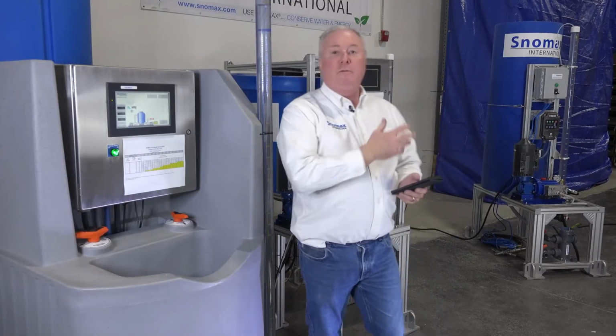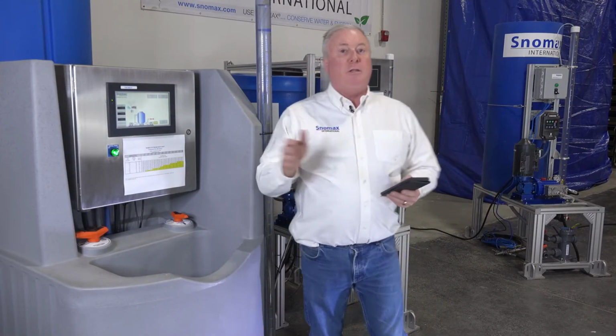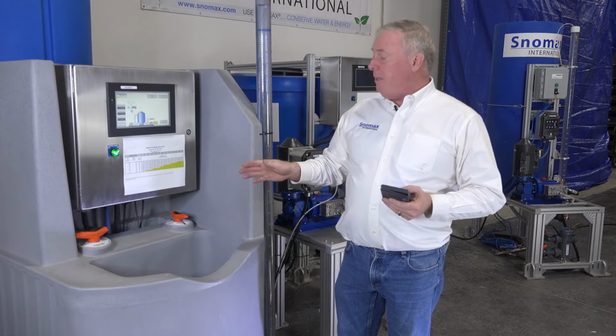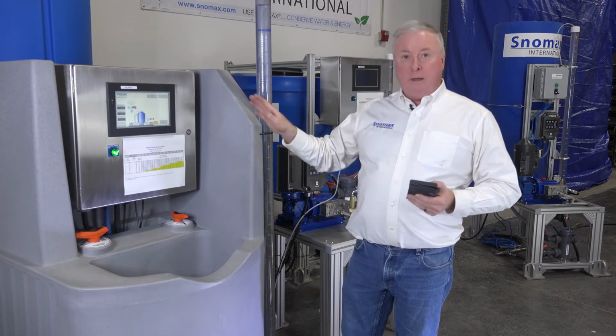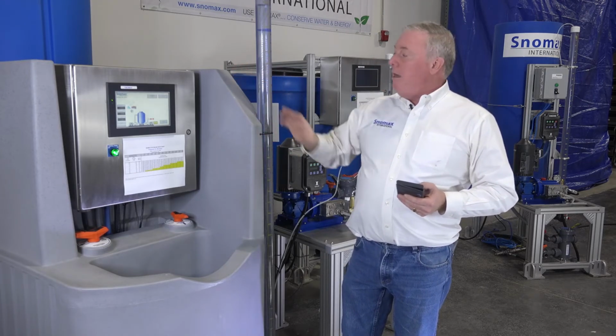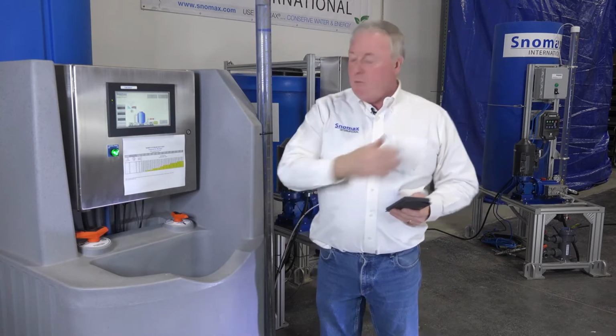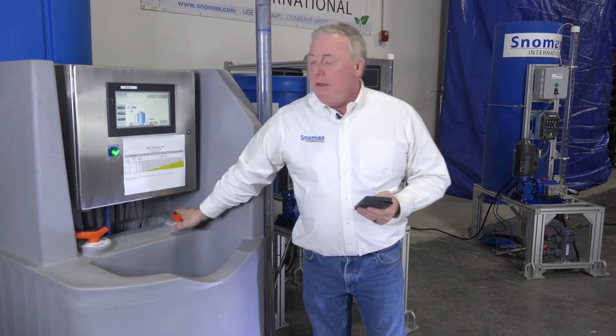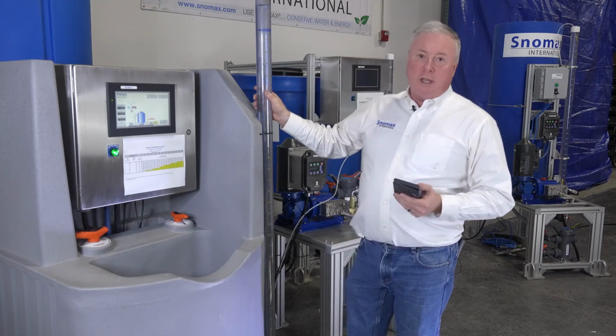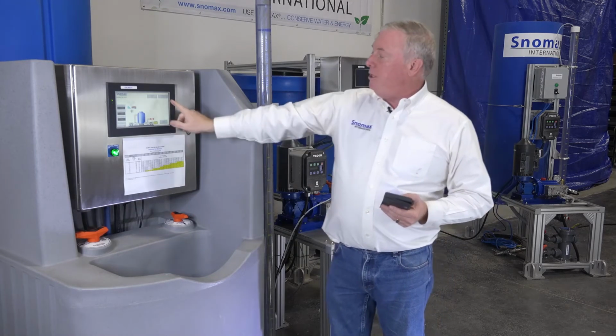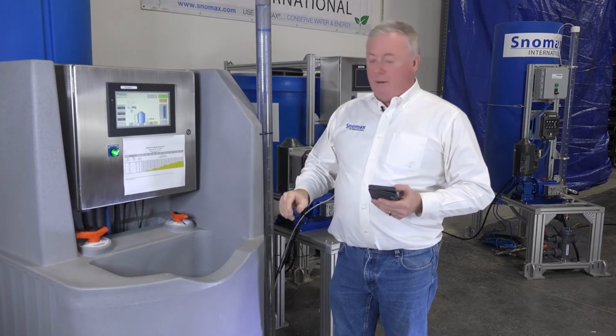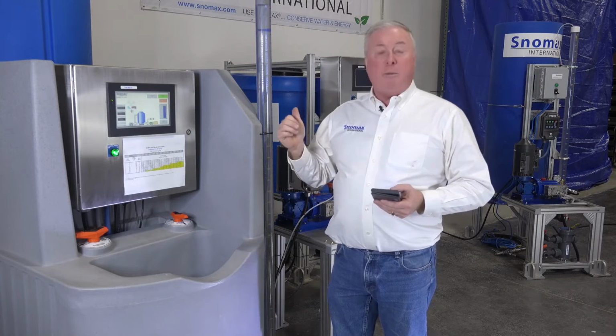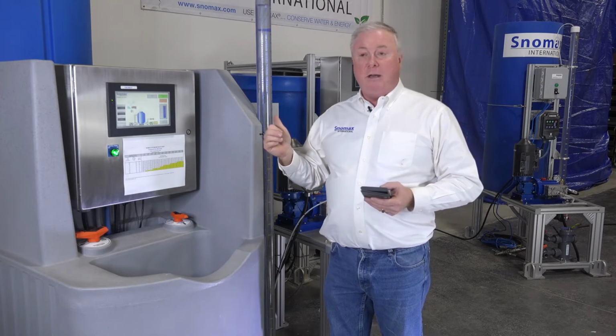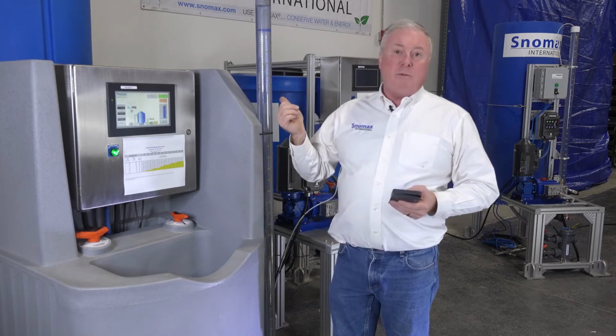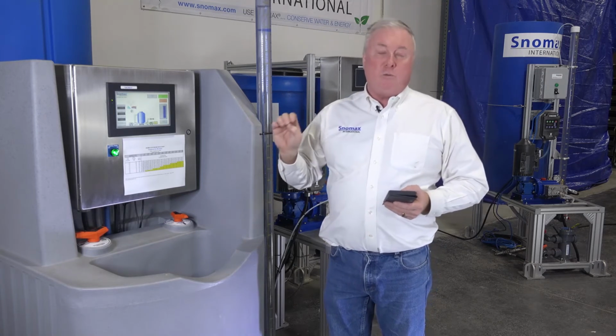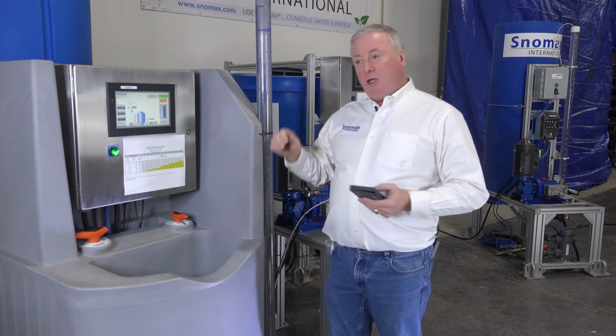All right, so we're moving on from our mid-size system up to the largest injection system in the Snomax fleet. This system has automated ball valves in the back that you can't see. It has a three-way valve, just like the last one we went to, but you can't see it, they're underneath. And the calibration column, just the same. So on this one, we're gonna start the pump. Since I'm simulating that we're pumping also against 2,000 gallons a minute, I've set up the pump maximum speed to be what I think is pretty accurate for that number. So it should match the other one.